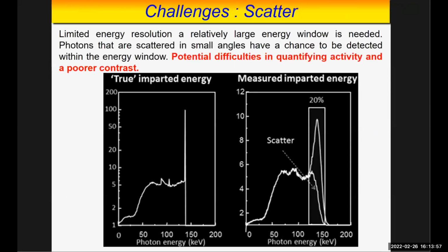Scatter: because of the limited energy resolution of the scintillator used in the imaging device, a relatively large energy window is needed to maintain good counting statistics. Some photons that are scattered through a small angle in the patient will therefore have a chance to be detected within the energy window. This leads to difficulty in quantifying activity and poor contrast, since these photons carry incorrect information about the point of emission. The scatter contribution depends on several factors such as photon energy, source distribution, and tissue composition, in addition to camera-specific parameters such as energy resolution and window setting.